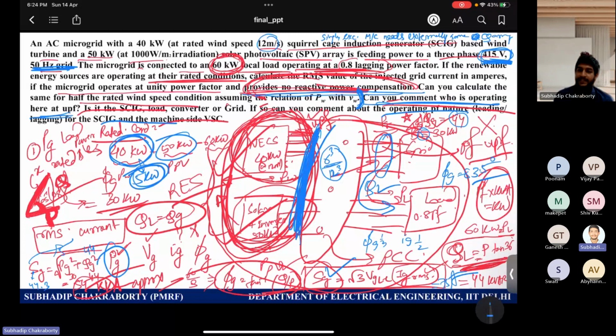But in the AC sources or the generators, if someone is delivering something, you take that to be positive. So if a generator is delivering lagging power factor reactive power, which is absorbed by the lagging power factor sources or loads, a generator is delivering reactive power and someone should absorb that reactive power. So who will absorb? Load will absorb. If load absorbs reactive power, it is taken to be positive. So a generator delivering lagging reactive power is taken as positive. But a generator taking in or absorbing reactive power is considered to be negative. Yes, sir, negative. Absorbing reactive power, that is leading, and that is taken to be negative.